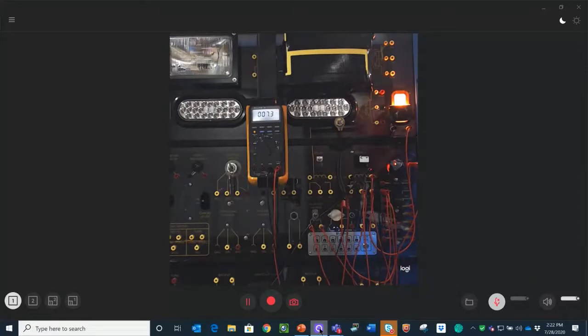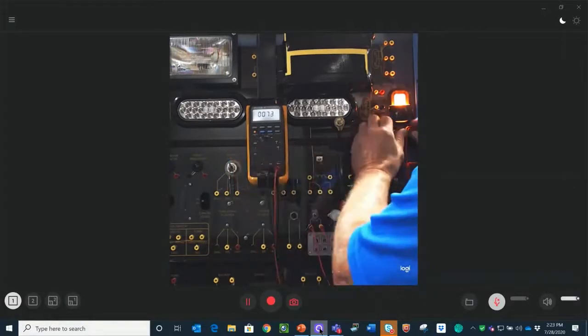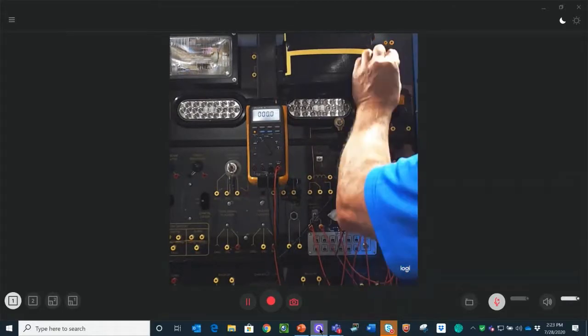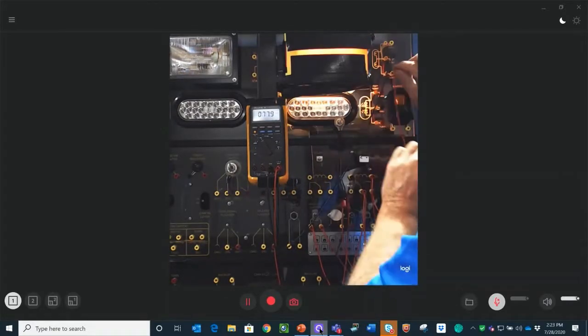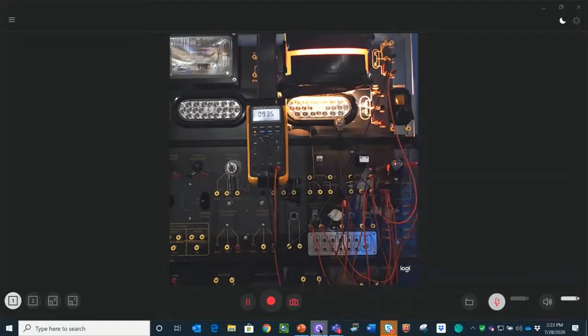Let's go back to the term rated load. When we're testing voltage drop of the contacts of the relay, we want the load going through the relay to be as close to the same load that it controls in the circuit. So watch my meter as I go up to change the 194 to the headlight. Now I have 93.4 millivolts, which is almost 1/10 of a volt.